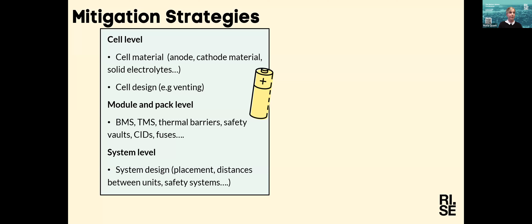At system level, design is very important for safety reasons. We can monitor and detect thermal runaway at an early stage by looking at temperature or gas detection, also electrical parameters. Ventilation can be a good way to avoid explosion, through active ventilation or deflagration panels. There are also methods for suppressing fires, both water-based systems and inert gas systems. But since lithium-ion batteries are used in a very large variety of applications, it's impossible to find one system that fits all, so it's very important that you test your system.